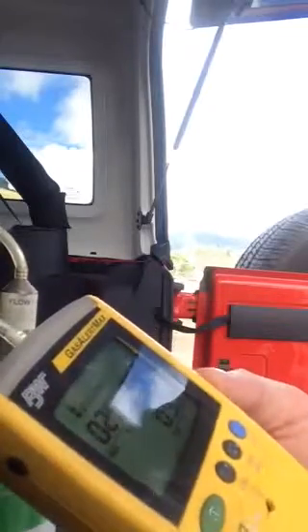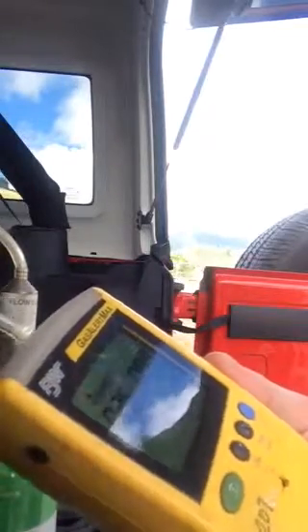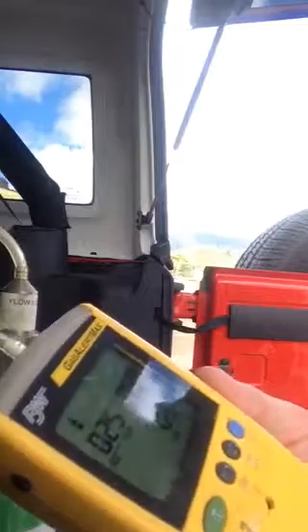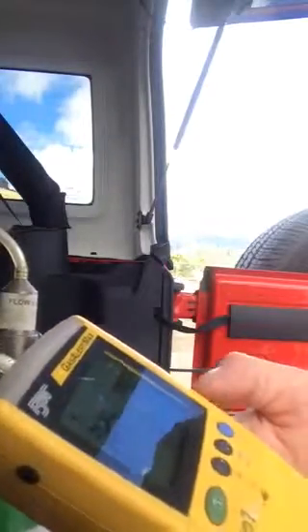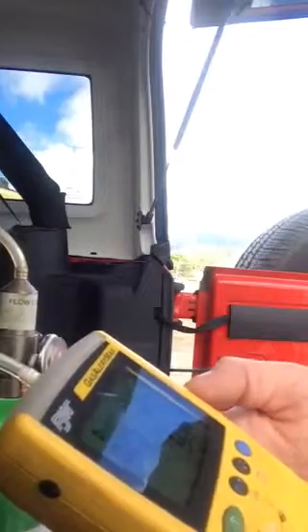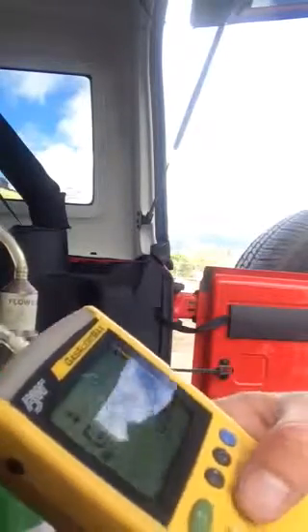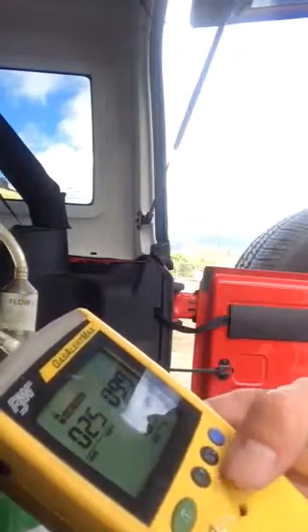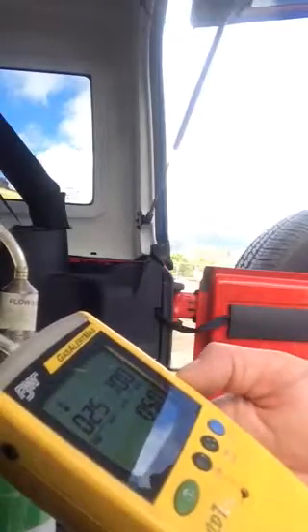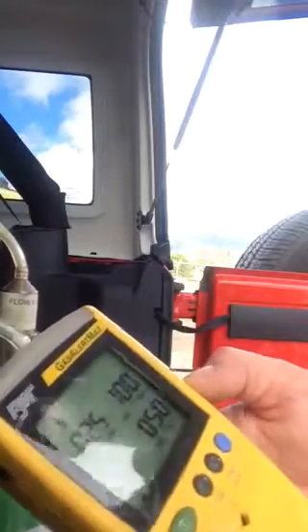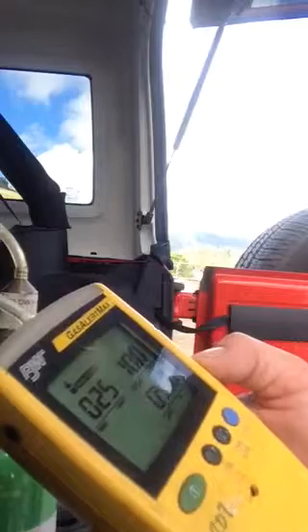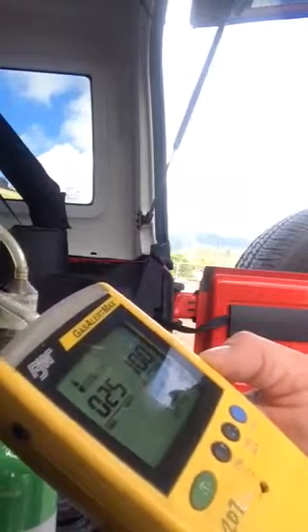Fortunately, this particular gas alert didn't require a passcode. Sometimes what will happen is you'll go into the calibration mode, and before you can calibrate, it'll ask for a 3-digit number. And you scroll up and down with the up and down keys to get the number. It's generally 898 is the number, but I don't think we have any of those here in Hawaii, so you should be alright.